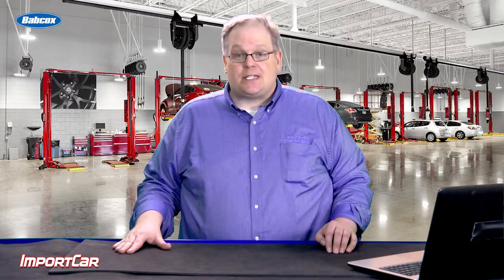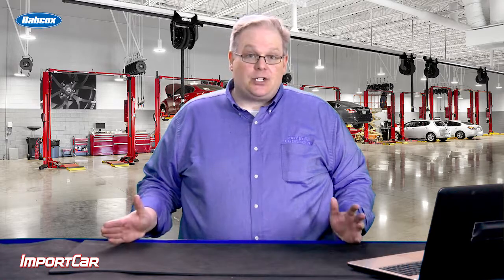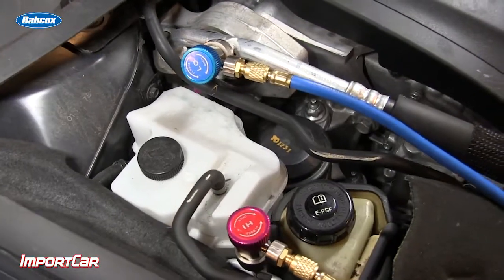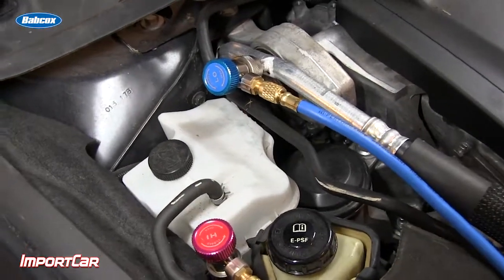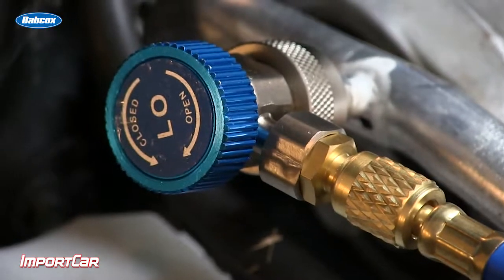Every year, the engineers get better and better at making an AC system work right, and they're doing this so it can operate with less refrigerant in the system. But for technicians, this means there's less of a margin of error when you're servicing the system - in other words, evacuating it and filling it up with new refrigerant and oil for the compressor.